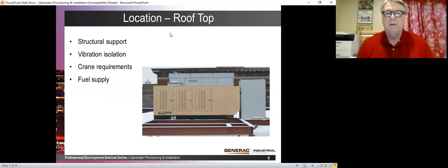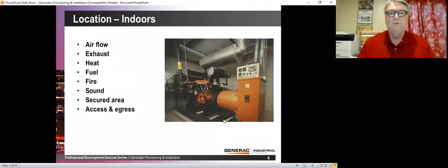And then you'll have to have a smaller day tank on the roof next to the generator. And so now it's going to require some discussions with the fire marshal, take a look at the roof material. It's not ideal, but it can be done. And then you have a pumping system, of course, that pumps to the day tank on the roof. You may need vibration isolation. Typically, the vibration isolation is already built into the generator, and you don't want to add anything else. But you can see here's a picture of a structural engineer who designed quite a little platform here to distribute the weight of the generator over a larger portion of that roof.